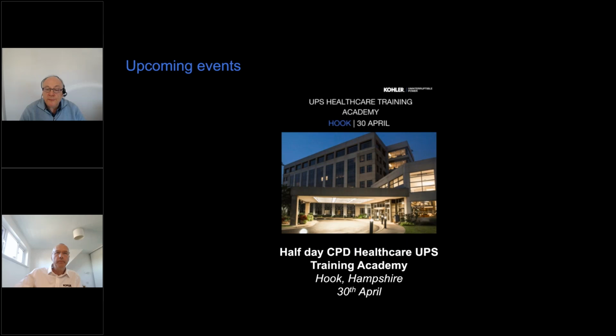Thank you. Another question. If the UPS has a single output connection, why do we need to put a protective device in the output if the UPS performs that function itself? Yeah, good question. You don't have to. What we do find is that people have to put a big UPS in to be able to clear the downstream protective devices, and then want to put a small cable in just to feed the load. In that case, you have to protect the cable.